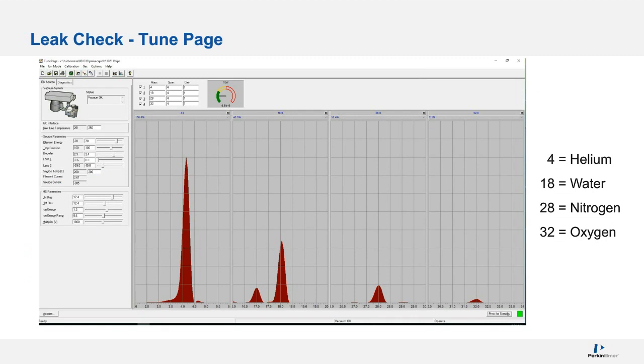I turn off mass 4 and mass 18, and I look at the ratio between nitrogen and oxygen, or 28 and 32. In air, it's a 4-to-1 ratio. If oxygen is lower than 25% when nitrogen is at 100%, that oxygen isn't coming from air. That nitrogen isn't coming from air. It's coming from somewhere else. Perhaps your helium tank has nitrogen in it.